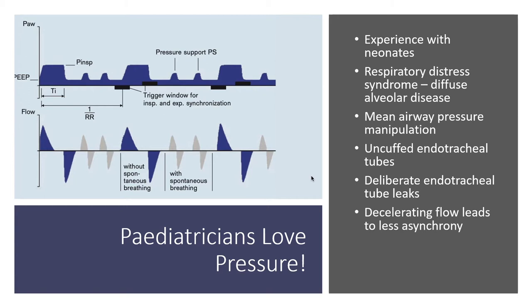We can also add that the decelerating flow you get from a pressure-style breath leads to a lot less ventilator asynchrony, as the flow arrives very quickly in the initial part of inspiration. This isn't so with a volume-style continuous flow breath.